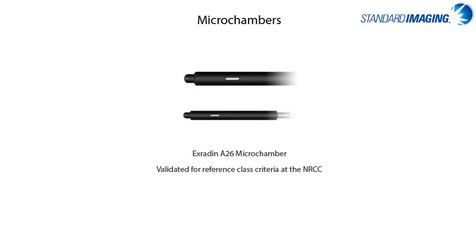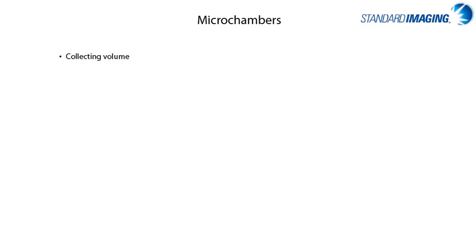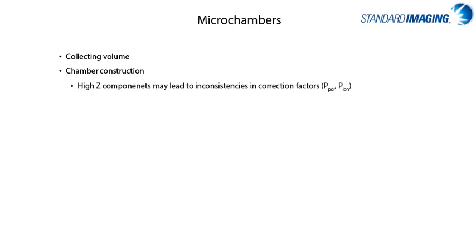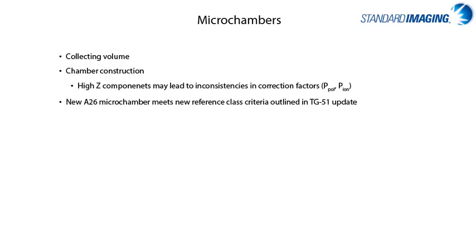First, I want to show the latest microionization chamber, which has been validated at the NRCC in Canada for many of the reference class criteria as described in the AAPM TG51 report. Standard imaging is the only manufacturer to provide fully-guarded microionization chambers, which means that the chamber settles rapidly, allows for meaningful corrections, and has minimal polarity and energy dependence.